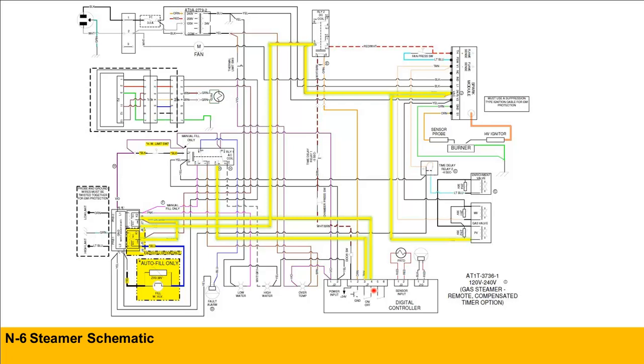Now, this is an output, so we'll actually be checking the pin. Now, as Dan mentioned, this is a grounded circuit, so we actually test the pin using our meter, AC volts, we'll test the pin to ground. Now, if we have 24 volts AC, the control board is good. If there is no 24 volts output, then we have a bad control board. At that point we'll give you a part number, the part's ordered, the part's replaced, and then the steamer, once again, will be operational.